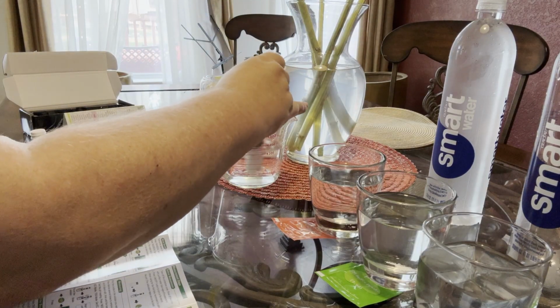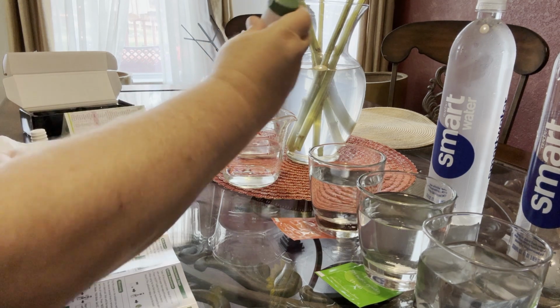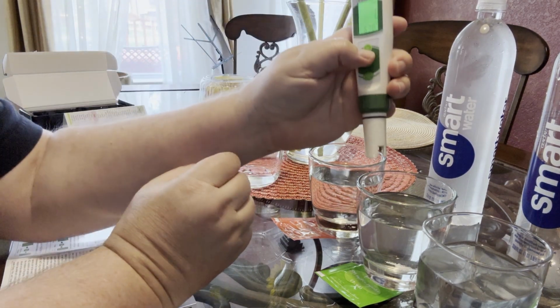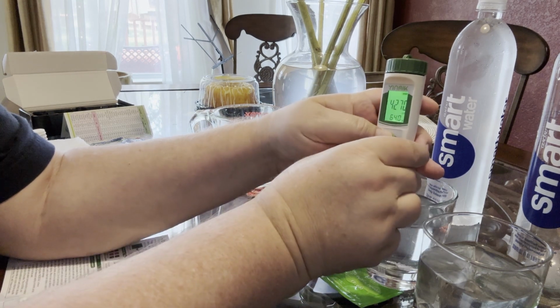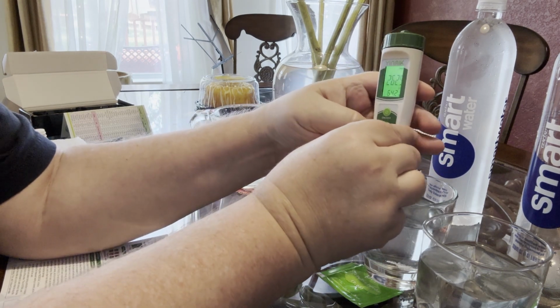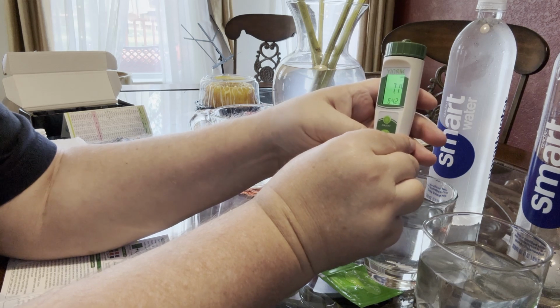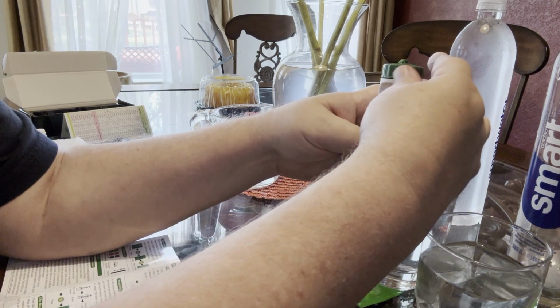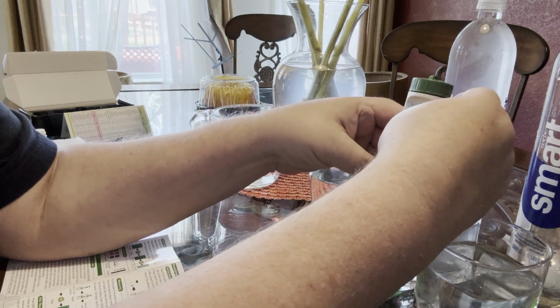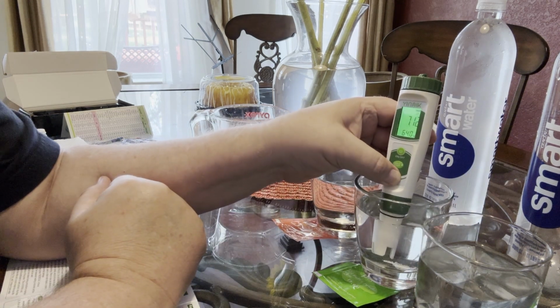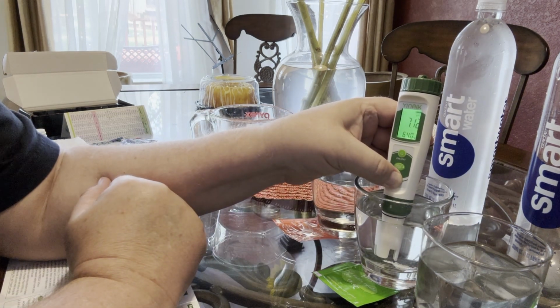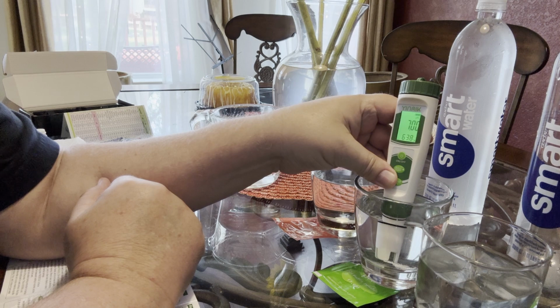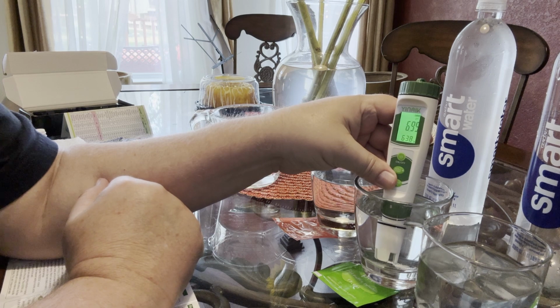Okay, we start by rinsing it in purified water. Then we put it in here. Oh, it's ppm, so I need to change that to pH mode. Put in here. And then once it stabilizes, we hold this down for 5 seconds. 1, 2, 3, 4, 5. It says cal, and that should blink. And 7.0.